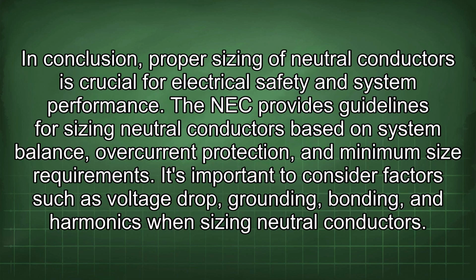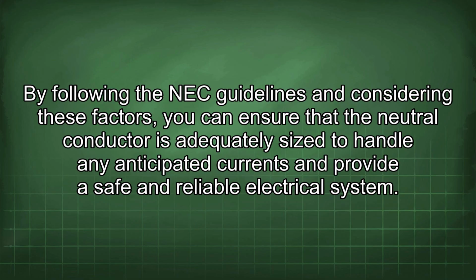In conclusion, proper sizing of neutral conductors is crucial for electrical safety and system performance. The NEC provides guidelines for sizing neutral conductors based on system balance, overcurrent protection, and minimum size requirements. It's important to consider factors such as voltage drop, grounding, bonding, and harmonics when sizing neutral conductors. By following the NEC guidelines and considering these factors, you can ensure that the neutral conductor is adequately sized to handle any anticipated currents and provide a safe and reliable electrical system.